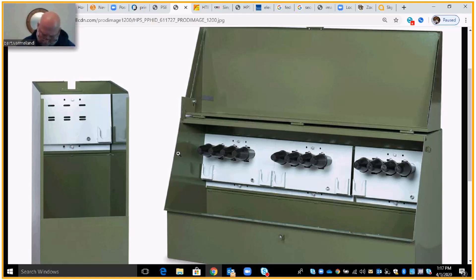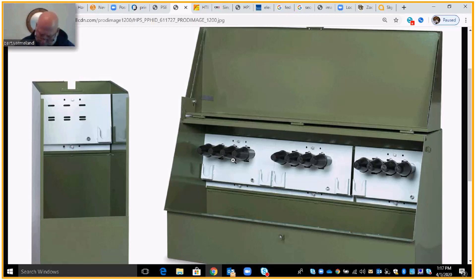You'll sometimes hear them called three-phase and single-phase junctions, and that's exactly their purpose. In the three-phase enclosure, I'm able to install A, B, and C phases in different module locations. These four bushings are all banded together behind and called a module. If I install A in position one, positions two, three, and four will all be A. Same for B and C. We follow the same industry rule: A, B, C — left to right. The feed in, as far as phase is concerned, is always on the left.